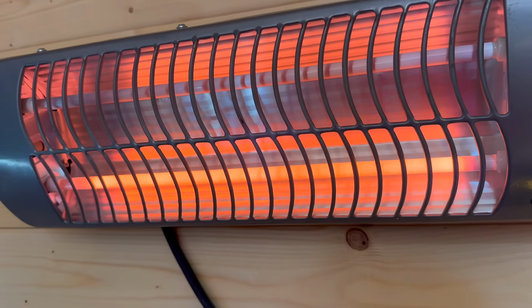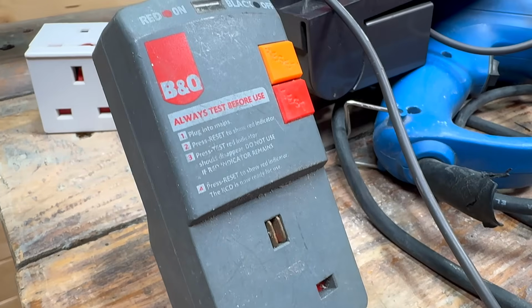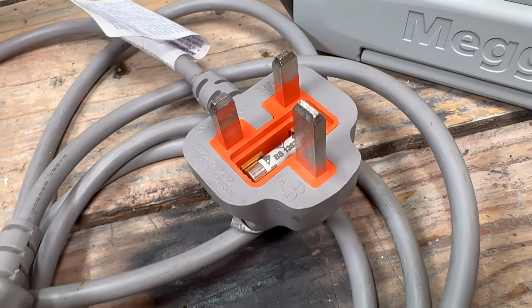Okay, let's get into it. We're going to be testing all classifications, including some variations of those classifications: RCD testing, power cord or IEC, and extension leads. This will, when appropriate, include calculations to confirm that our readings are suitable and within defined limits. And we're going to start with class 3.